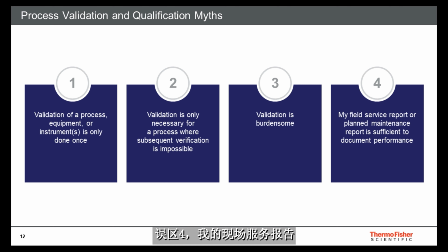Myth 4. My field service report or planned maintenance report is sufficient to document performance. No. To understand why a service report or maintenance protocol cannot stand in for a qualification, consider the intention of the document. This is how a potential investigator will establish the utility of the documentation being provided by a firm. The intent of a service report is to document the scope of service event required. A maintenance protocol's intention is to document that the manufacturer's recommended maintenance activity has been performed.